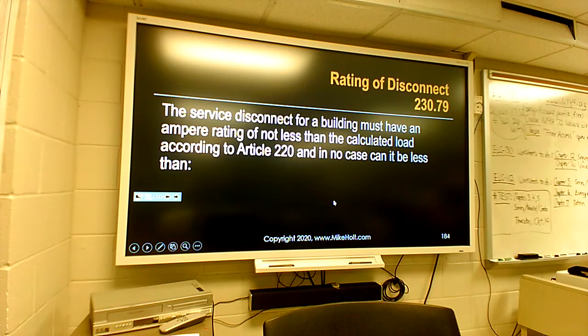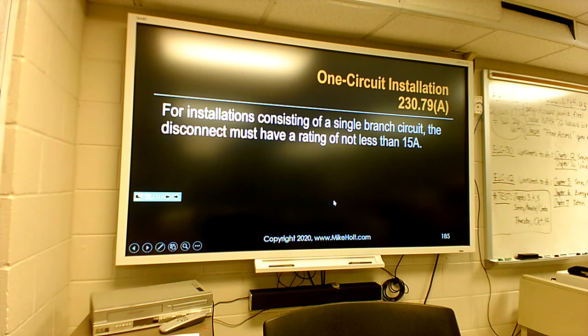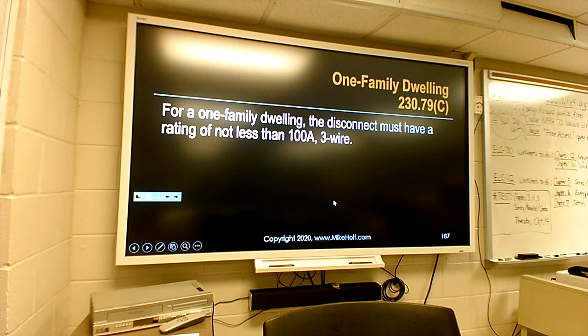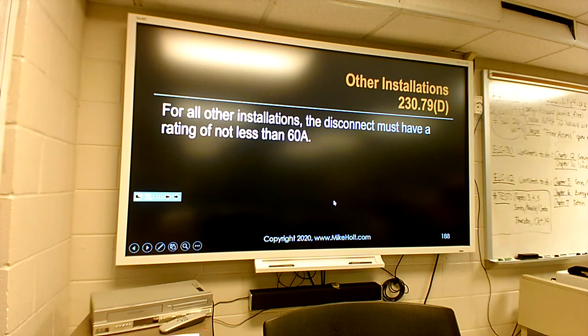Your service disconnect must have an ampere rating not less than the calculated loads that we went over back in 220. For a branch circuit, a disconnect must not have a rating less than 15 amps. For a two-circuit installation, no less than a 30 amp disconnect. For a one-family dwelling, your disconnect must not be rated less than 100 amp, 3-wire. All other installations, no less than 60 amps, maybe like for a workshop or something like that. That's outside.